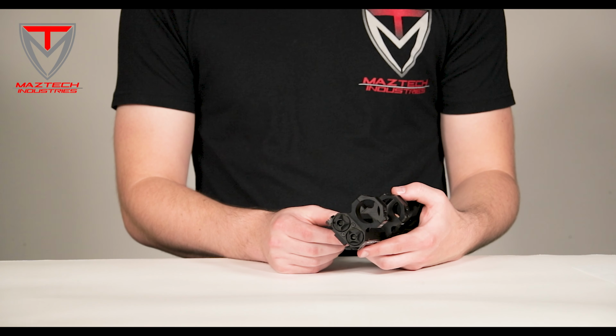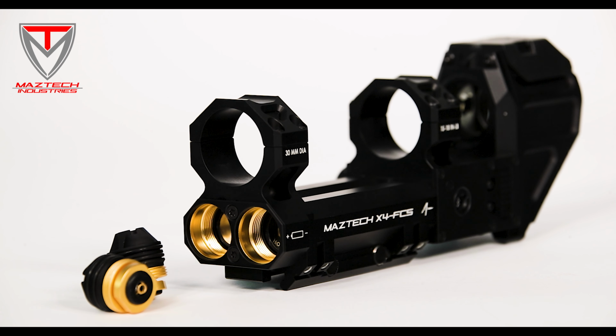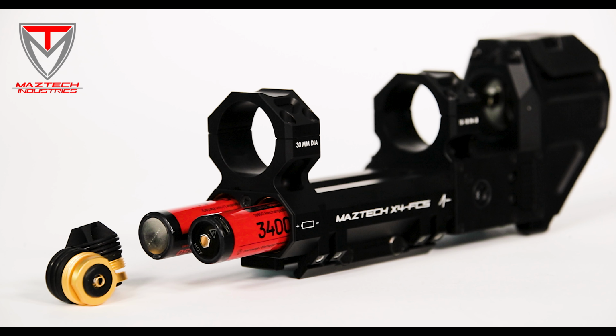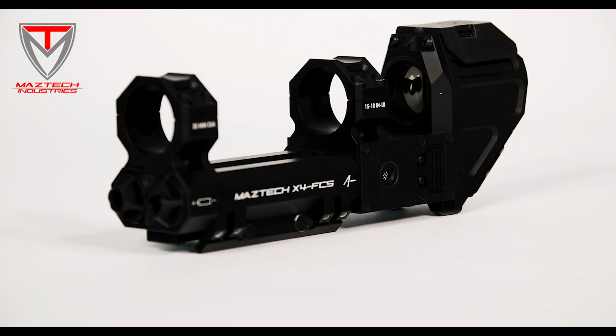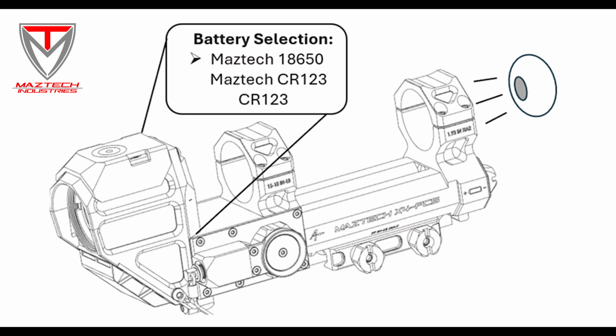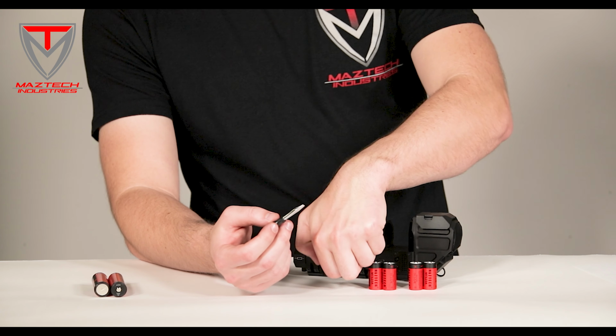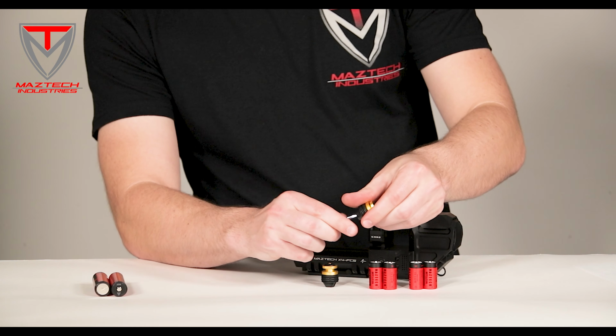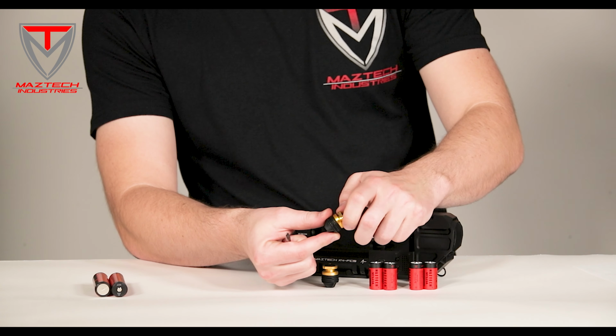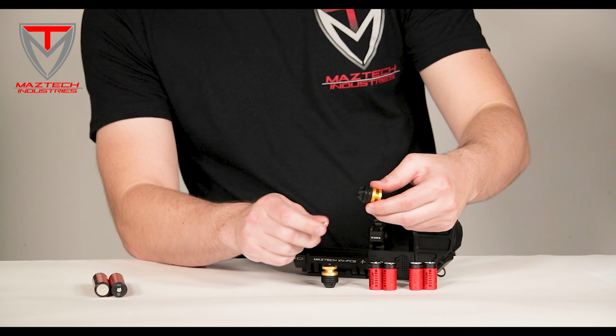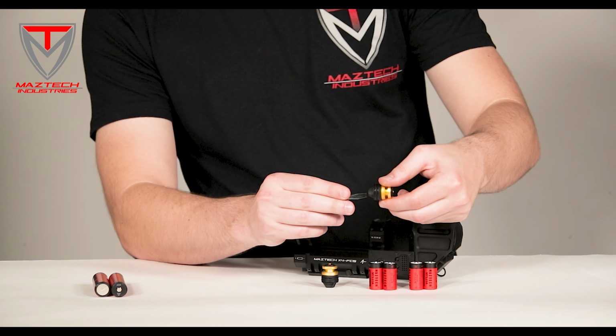To install the batteries, start by unscrewing the battery caps by hand. Place the Maztech batteries into the FCS, ensuring the proper polarity is indicated on the housing. Hand tighten the battery caps. Once the caps are secure, look at the display and confirm that the arrow is selecting Maztech 18650 as the battery type. Press the button to confirm your selection. For alternate battery options, you can also use 4 CR123 batteries. Detailed instructions on adjusting the battery caps for different batteries are available in the online manual.